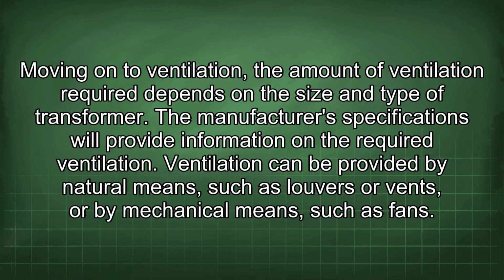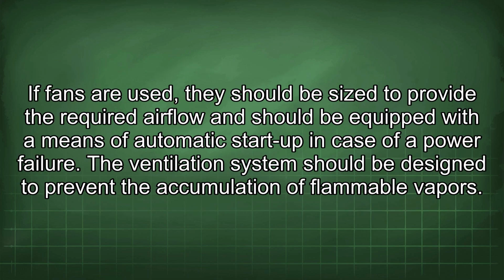Moving on to ventilation, the amount of ventilation required depends on the size and type of transformer. The manufacturer's specifications will provide information on the required ventilation. Ventilation can be provided by natural means such as louvers or vents, or by mechanical means such as fans. If fans are used, they should be sized to provide the required airflow and should be equipped with a means of automatic startup in case of a power failure.